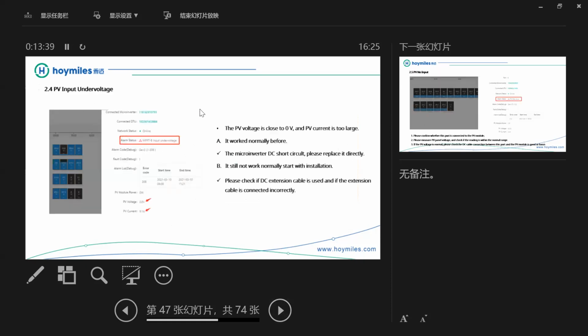If the alarm shows input under voltage, there are two situations. The PV voltage is close to 0 and the PV current is too large, but it worked normally before. It means the microinverter DC is short circuit. Please replace it directly. But if it still does not work normally, start with the installation. It means a DC extension cable is used, and if the extension cable is connected incorrectly, please check that.